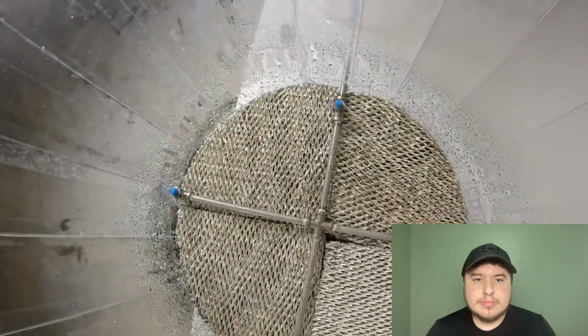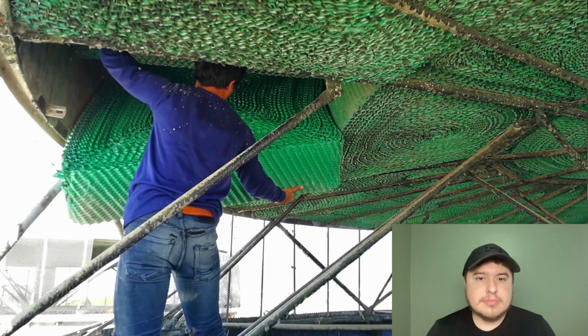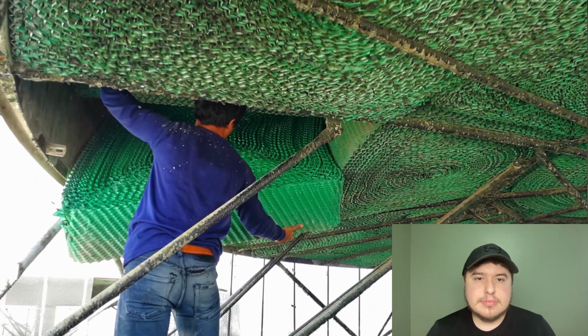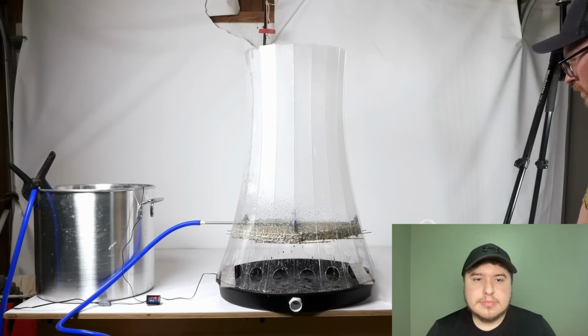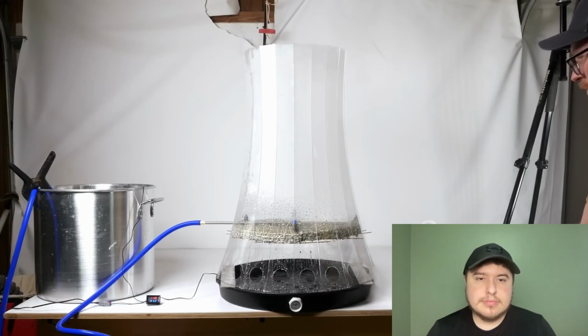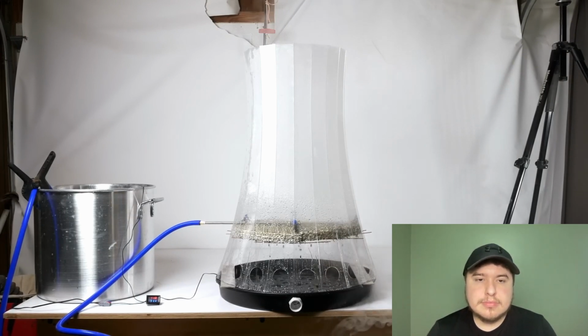This is called fill. I'm just using a dehumidifier pad, but in an actual cooling tower, the fill is usually a layer of plastic, carefully designed to maximize the surface area of the water in the system. It does this by forcing the water to either splash into tiny drops or form thin sheets as it falls downward. The goal is to expose as much surface area of the hot water as possible to the air flowing through the tower. Water drips down, air flows up. The pros call this counterflow, and it's the trick to the whole process. Actually, you can use crossflow as well, but let's jump over that rabbit hole for now.